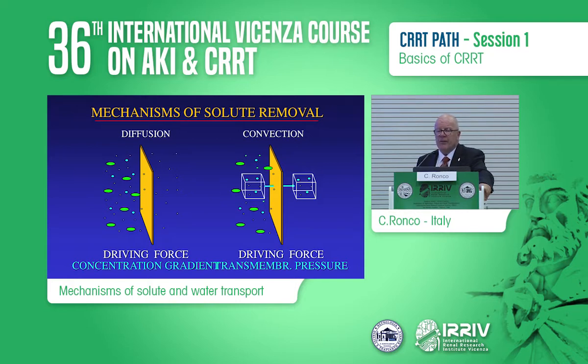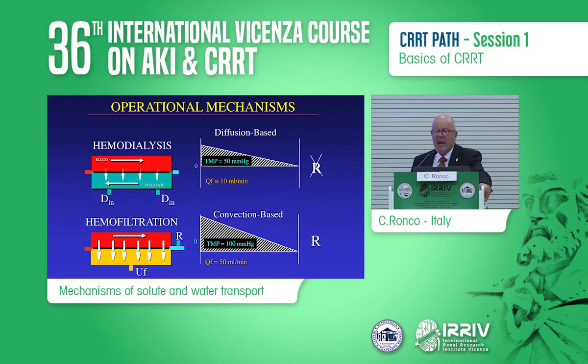The driving force of convection is the transmembrane pressure, which makes it possible to transport some solvent across the membrane and then bring solutes with it. The main mechanism of diffusion is used in hemodialysis, where you have dialysate and you don't need any replacement solution.